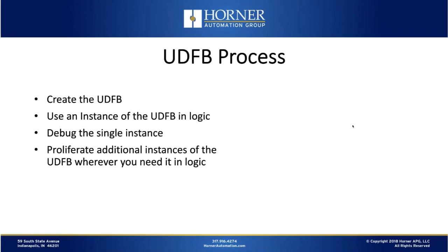Okay, so what's the process for using UDFBs look like? Well, first you need to create the function block. You're going to use an instance of the function block in your logic somewhere. You're going to debug it, of course. Again, as I mentioned before, you don't want to be replicating buggy logic. You want to prove it out, and you'll do that by debugging an instance of the logic. And then once it's well proven, you can proliferate that code through that user-defined function block with additional instances in the same project, or maybe in the next project, by saving it away and recalling it later.